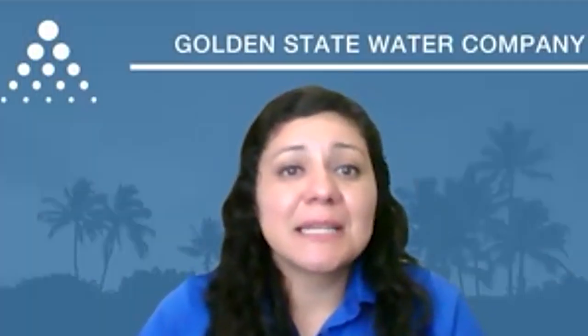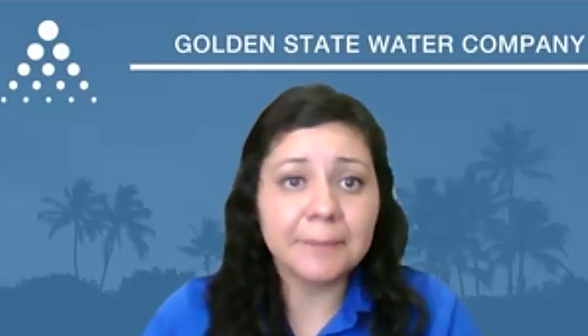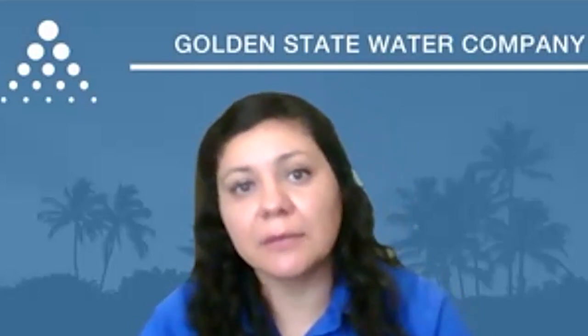Yeah, so the real-time selenium data has been invaluable in helping us manage heavy metal exceedances. Although grab samples are still required for compliance purposes, we have to wait to hear back from the lab, and as a result, plant adjustments are delayed. With the online selenium analyzer, the live data is continuously available and we use it to adjust the treatment plant in real time. Having continuous access to selenium readings has helped us enhance plant performance by adjusting the amount of source water treated while maintaining compliance with all state and federal standards.